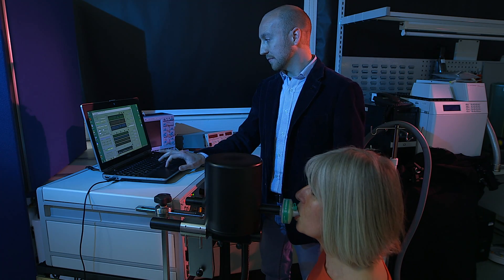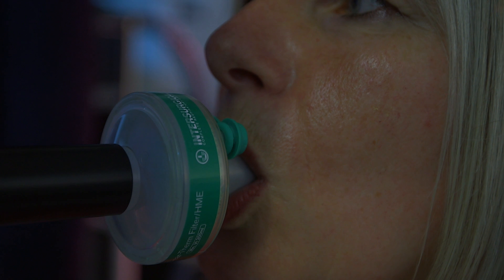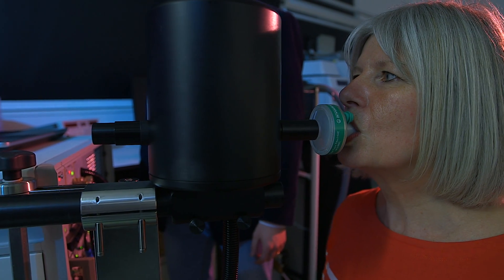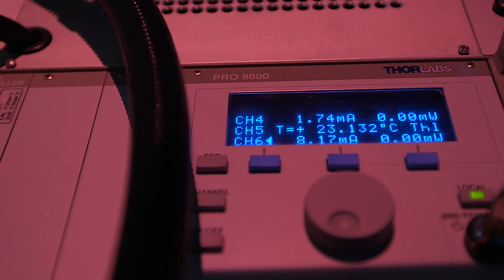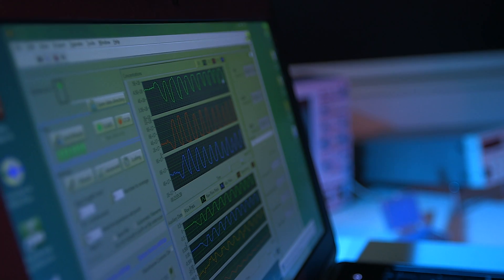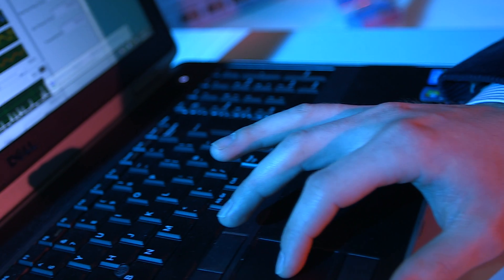Physiologists had a problem: they wanted to learn directly how the human body uses oxygen, what the rates of consumption are and how these change with particular conditions. As the volunteer breathes in and out through the device, you will see changing composition of the oxygen, carbon dioxide and water concentration within the airways on a real-time basis. The core of this device is that it combines these simultaneous measurements and produces an estimate of the oxygen uptake and CO2 production on a breath-by-breath basis. This is something quite challenging to achieve, which is not currently done during surgery.